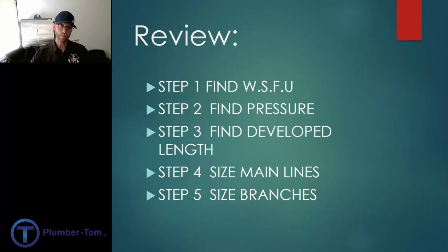So to review, here are our steps. Step 1, find the water supply fixture units for all of the fixtures in the building. Step 2, find the system pressure. Step 3, find the developed length for the system. Step 4, use the tables to size the main lines. And step 5, use the tables to size the branches.